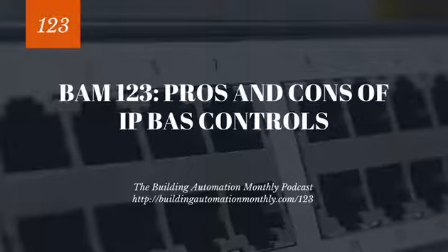Now, what happened is, you've got this supervisory device, and it's acting as a gateway between this serial network, RS-485, RS-232, so BACnet MSTP, Modbus RTU, those kinds of things. And it's translating it to BACnet IP, Modbus TCP, etc. Well, with these IP controls, now we're eliminating that layer.